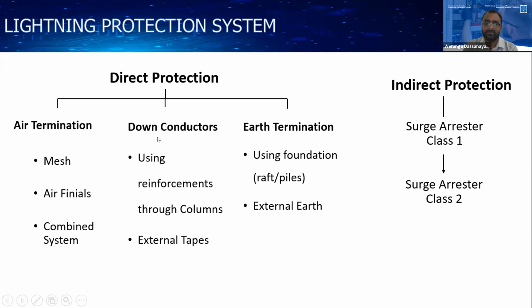Then down conductor means the absorbed lightning you should securely pass to the ground. That means the lightning we have absorbed from the air termination system should be securely passed to the ground. For that, you are using a down conductor. As a down conductor, some buildings may have used the reinforcement inside the column at their construction stage, or you can use an external conductor to pass that current to the ground.